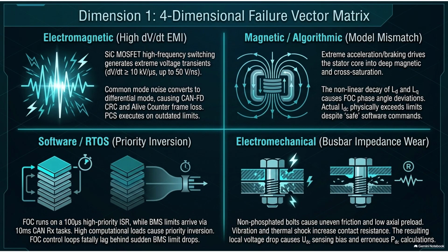Oh, wow. So without some kind of complex real-time compensation, you get a massive power limit conflict. Exactly. The software calculates that it is operating safely within, say, a 300 kilowatt limit. But the physical reality is that the inverter is actually pulling 400 kilowatts. Which is stressing the battery cells right toward thermal runaway. Yes, it's extremely dangerous. So the software thinks it's sipping water, but the physical hardware has basically opened a fire hydrant. That's exactly what's happening.